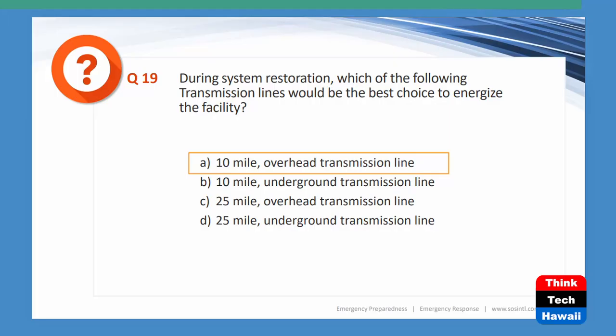So a 10-mile overhead transmission line is the best. It's less capacitive, right? A 10-mile underground transmission line is worse. A 25-mile overhead transmission line is also pretty bad when it comes to generating VARs and raising your voltage. And then the worst one of all is the 25-mile underground transmission line. So that'll be the worst of all of these when it comes to really affecting and raising your voltage in the weak system.